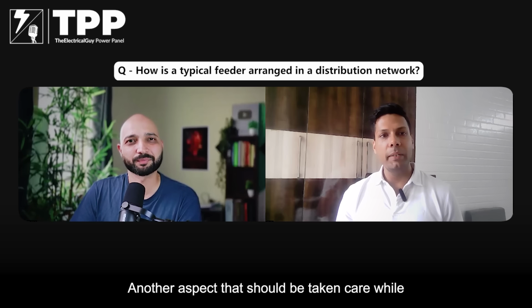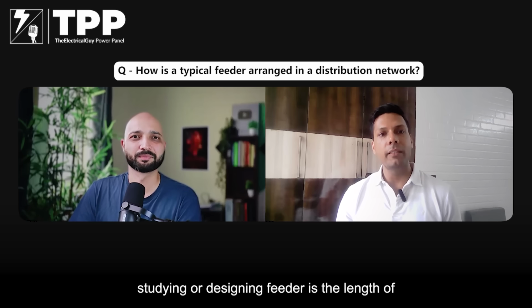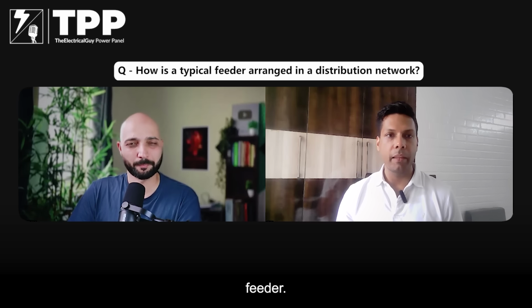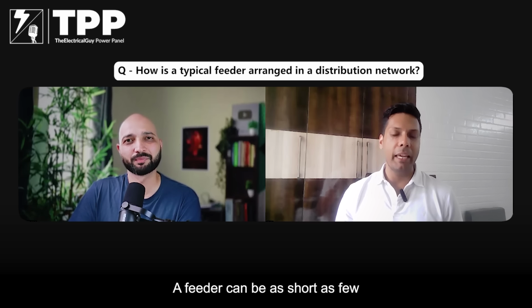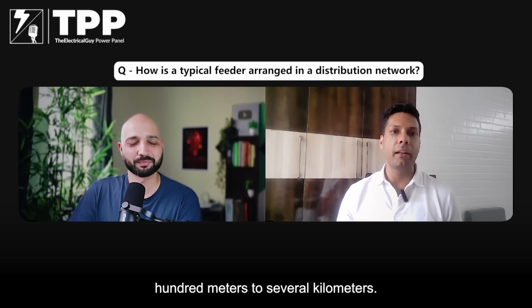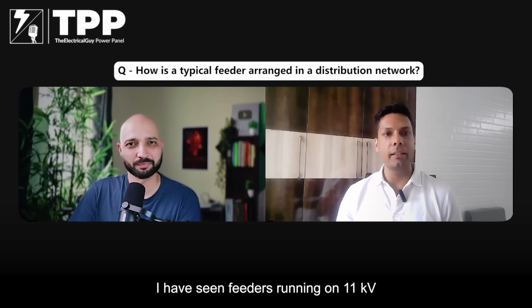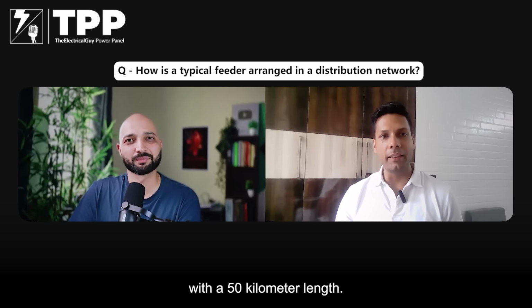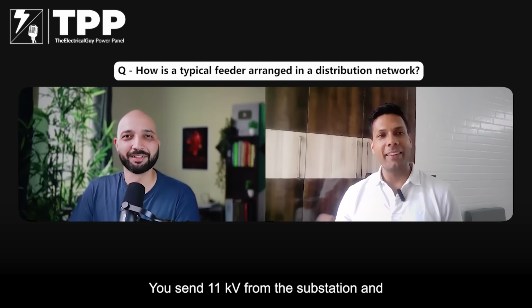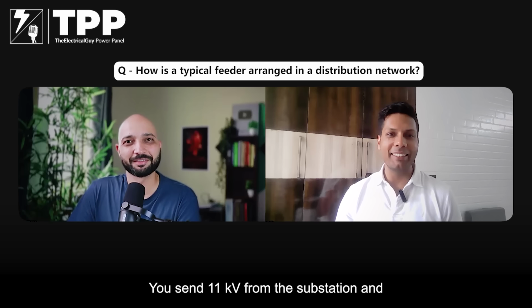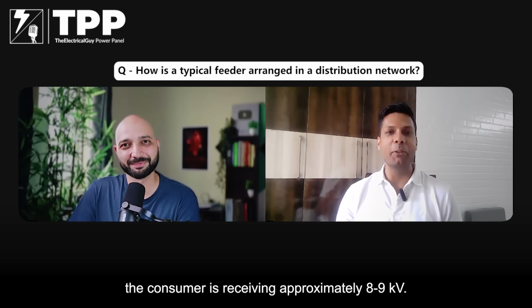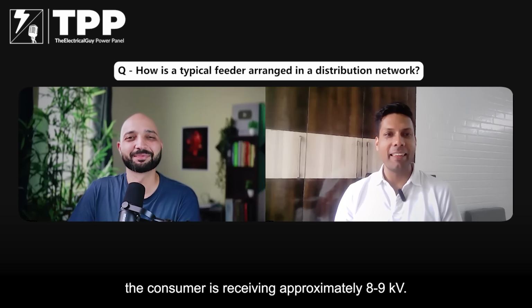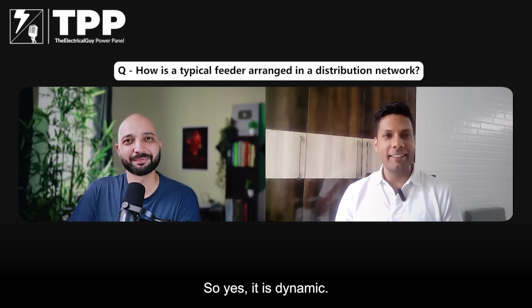Another aspect that should be taken care of while studying or designing a feeder is the length of the feeder. A feeder can be as short as a few hundred meters to several kilometers. I've seen feeders running on 11 kV with a 50-kilometer length. Oh, that's huge. So you send 11 kV from the substation, and the consumer is receiving approximately 8 or 9 kV. So yes, it is dynamic.